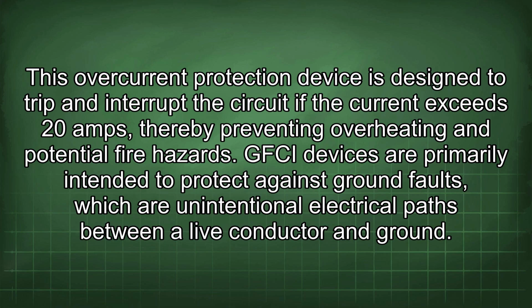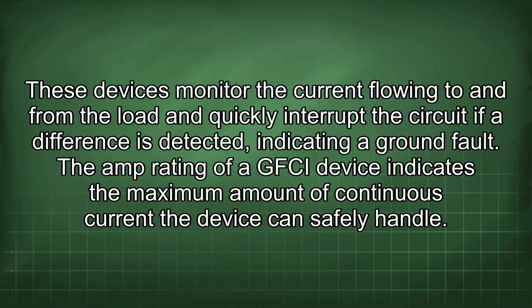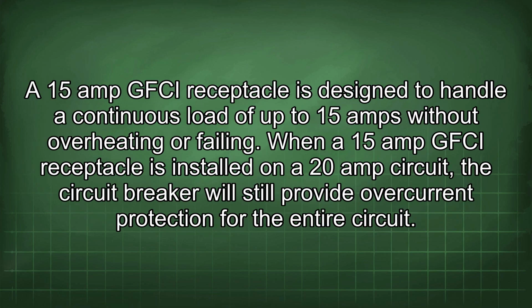GFCI devices are primarily intended to protect against ground faults, which are unintentional electrical paths between a live conductor and ground. These devices monitor the current flowing to and from the load and quickly interrupt the circuit if a difference is detected, indicating a ground fault. The amp rating of a GFCI device indicates the maximum amount of continuous current the device can safely handle. A 15-amp GFCI receptacle is designed to handle a continuous load of up to 15 amps without overheating or failing.